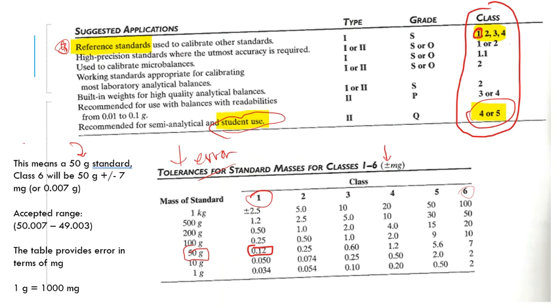Now, if I go to class 6, which would be more of a student type of use, then class 6 gives me a plus or minus tolerance, an error. And what that means is that that error is plus or minus 7 milligrams, not 0.12 milligram, 7 milligrams. This calibration weight could weigh 7 milligrams less, or it could weigh 7 milligrams more than what is stated on the calibration weight. Now, for student use, for academic use, that might be perfectly okay. I mean, we don't probably need to go better than that, but for industry grade calibration weights, this is not going to call the shots for us. We do desperately need that class 1 whenever we can get a hold of them.